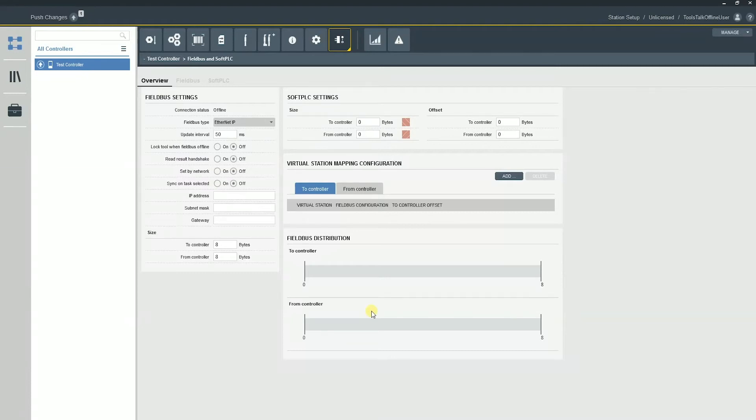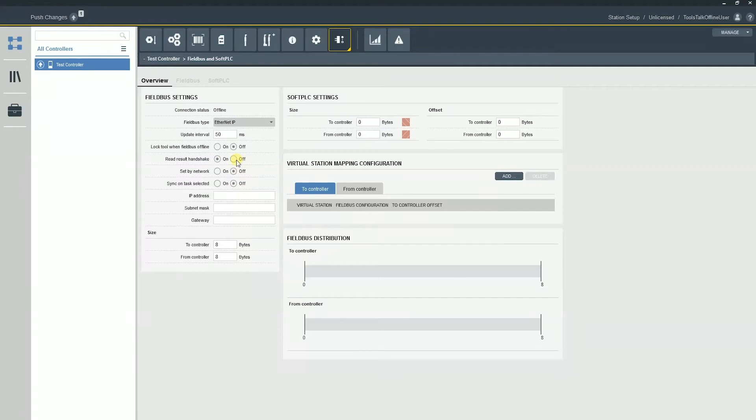Now let's talk about read result handshake. This is a very important variable to talk about. The reason it's very important is by simply turning on the read result handshaking, we can cause some issues with reporting over the fieldbus. Essentially what read result handshaking is, is every time we receive an okay tightening from the controller, that is going to send through a variable to the PLC and they're going to increment it.